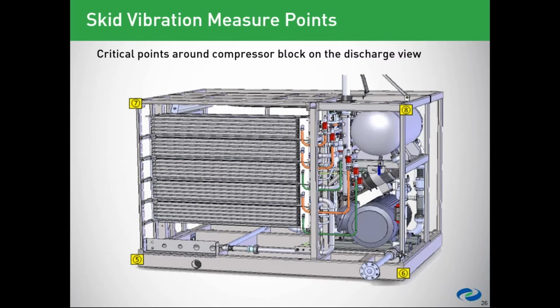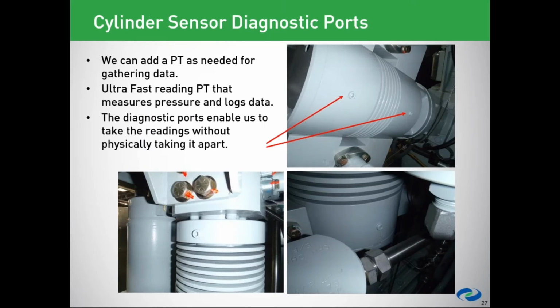So this is a cylinder sensor diagnostic port slide. We can add high-speed PTs to this for gathering data, an ultra-fast reading PT that measures pressure and logs data. This can be put into a scale and looked at for fault finding, for various things, just to see how, in some cases, the rings and piston rings are wearing inside of the compressor. And basically, it's an additional point. We don't have to take the cylinder apart to find out what's wrong inside. So this is something better.